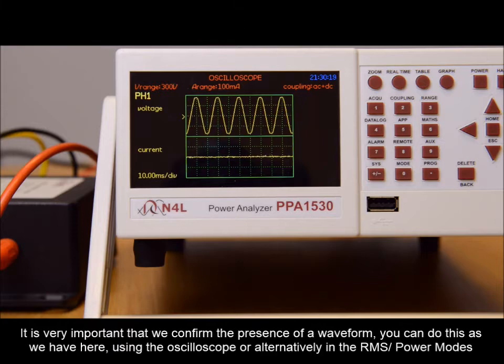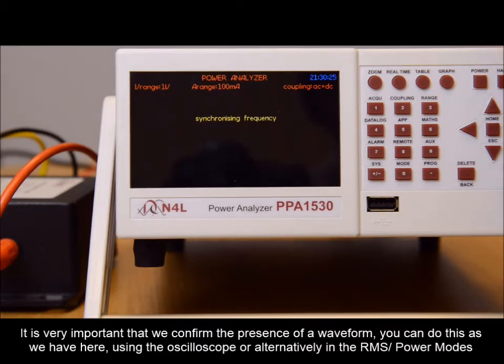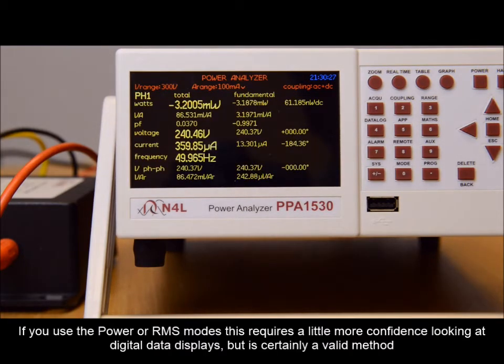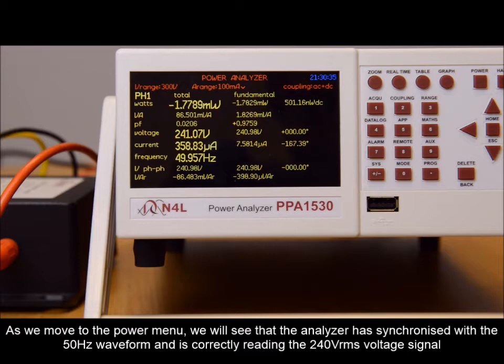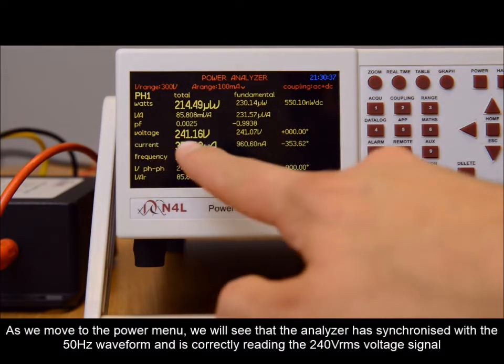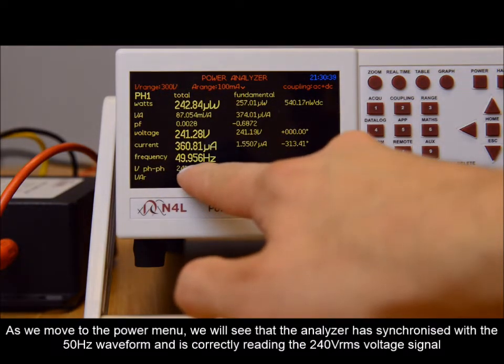It is very important that we confirm the presence of a waveform. You can do this as we have here, using the oscilloscope, or alternatively in the RMS or power modes. If you use the power or RMS modes, this requires a little more confidence looking at digital data displays, but it's certainly a valid method. As we move to the power menu, you will see that the analyzer has synchronized with the 50 Hertz waveform and is correctly reading the 240 volt RMS voltage signal: 50 Hertz, 240 volt RMS.